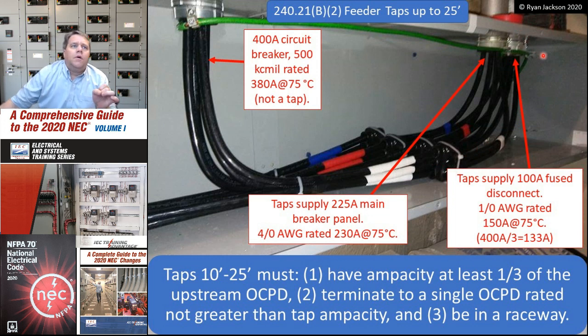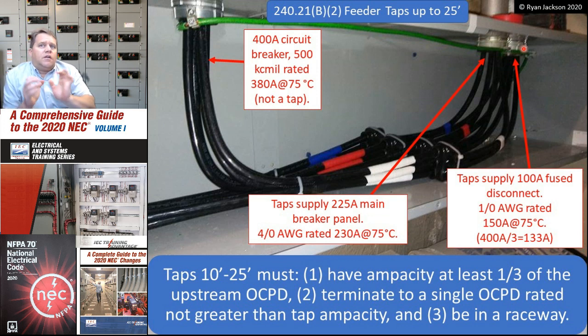Yeah, no problem. No problem at all. It's just that the wires have to be a little bit bigger. And the reason for that is, let's think about it. Going longer than 10 feet, going from 10 to 25 feet, I've added more resistance. We do have to remember that at a certain point it would get crazy enough that I would lose my ground fault and short circuit protection.